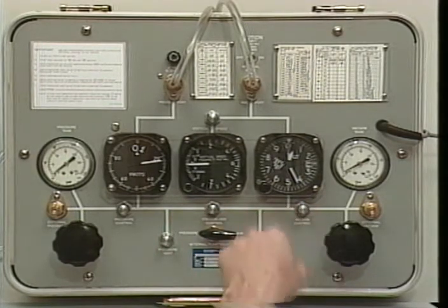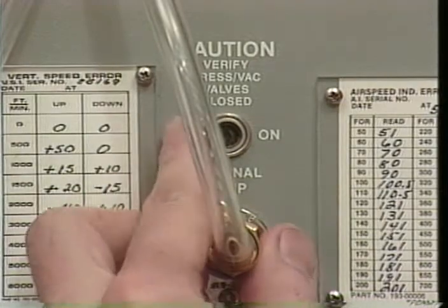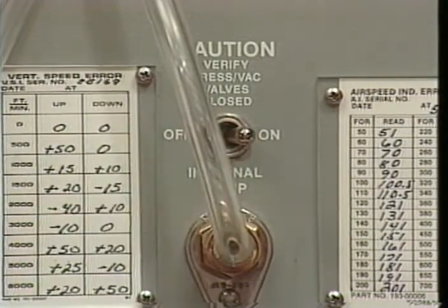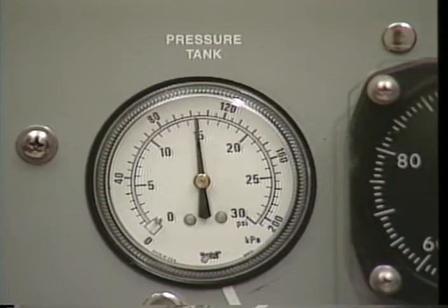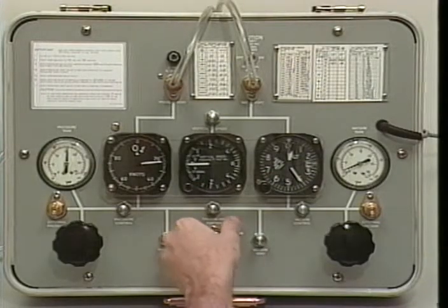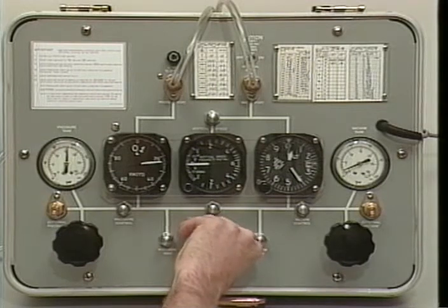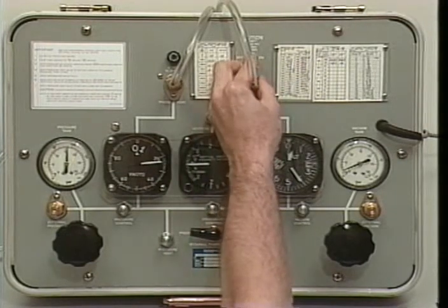Turn on the internal pump switch, or use hand pumps, and pump the pressure tank reservoir to at least 15 psi, as indicated by the pressure tank gauge. Turn on the internal pump, or use hand pumps, to increase the vacuum in the vacuum tank to 25 inches.